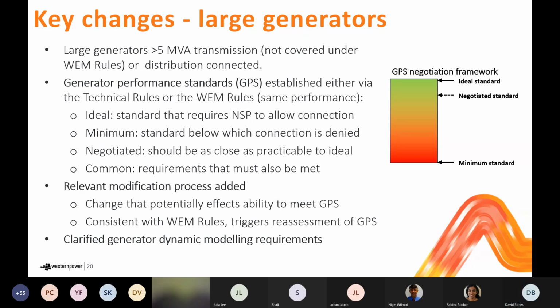The other elements that make up the generator performance standard framework are the negotiation criteria and the common requirements. So just to bring everyone up to speed on what we mean by that. Common requirements need to be met regardless of the level of performance articulated in your negotiated standard. And you'll see when we step through each of the 11 requirements on the subsequent slides what's meant by a common requirement. And then there's a negotiation criteria. So there's a framework for negotiating the negotiated standard, but then for some specific technical requirements, there's additional guidance given as to factors that need to be considered through the negotiation process.